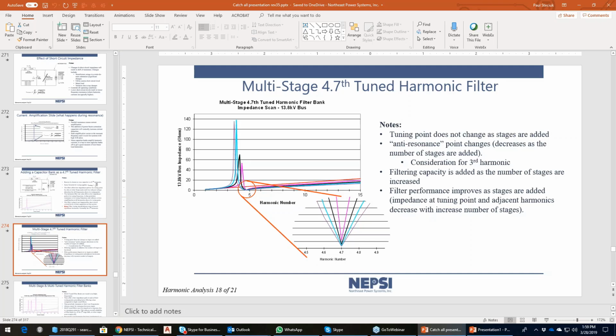So it's good for filtering low levels of harmonics, I would say, active filters, and they're very fast. They can provide reactive power on a very quick basis also, and it is highly flexible. Some of the units I've looked at have the ability to dial in a range of frequencies which you want to eliminate. But with the use of active filters, you need to be careful if you're applying those in conjunction with capacitor banks. You would always want to have a detuned capacitor bank or a filter bank tuned to 4.7 or below if you're going to supply active filtering with some type of passive reactive power compensation.